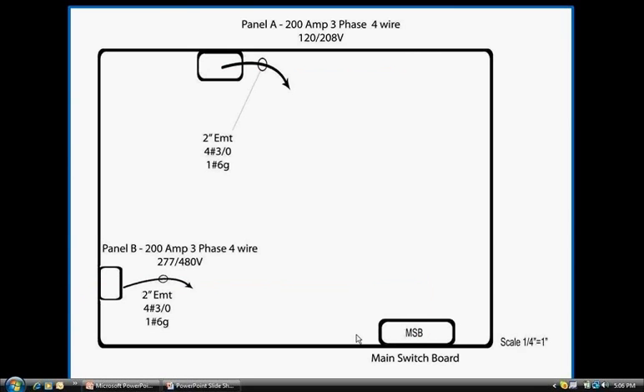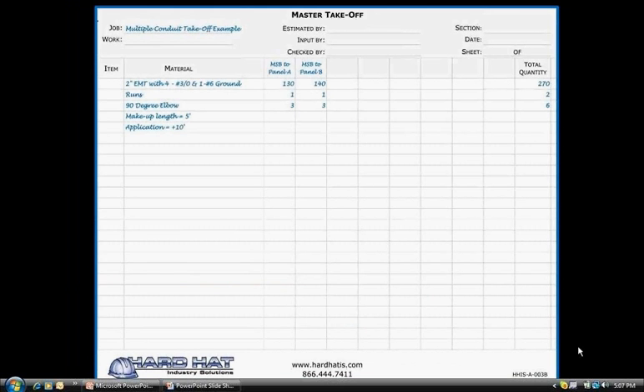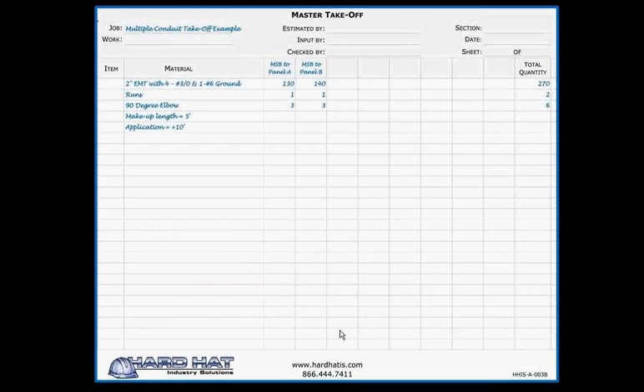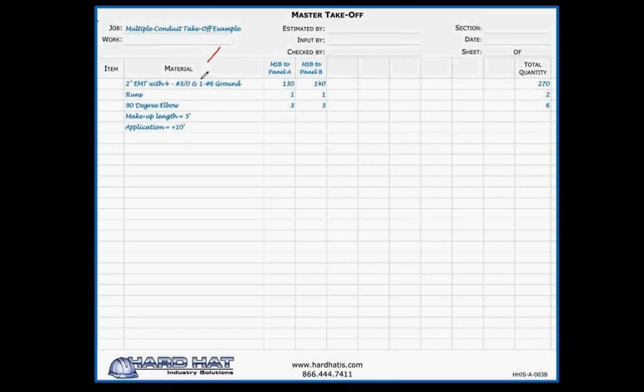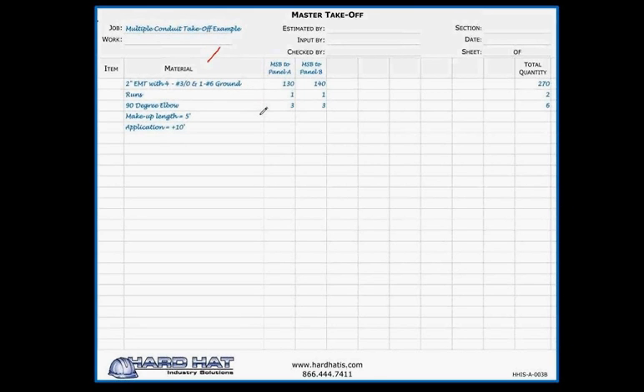Let's look at the takeoff sheet and allow me to explain how I have set it up. Notice on the left side under material, I wrote the conduit and wire information, the number of runs, conduit application, etc. Since there are multiple conduit runs, in this case two runs, which are the same size with the same size and number of conductors, I'll also be able to enter them at the same time into our estimate using Red Rhino. However, I want to record each feeder conduit separately on the takeoff sheet. I take them off separately in case there are any future changes required in the estimate. If there are changes, I can easily know the length of each feeder conduit to make changes more efficiently and effectively.